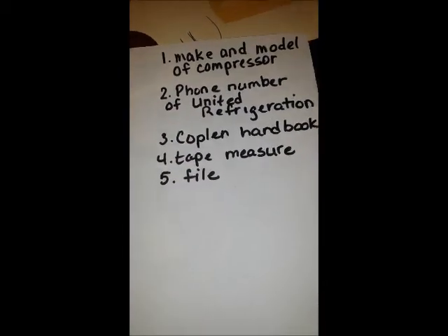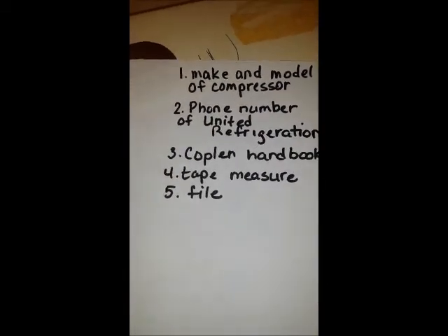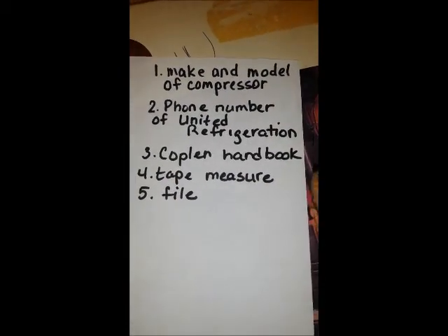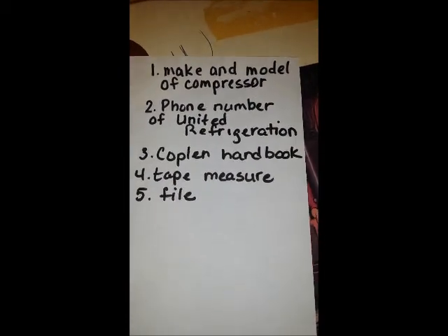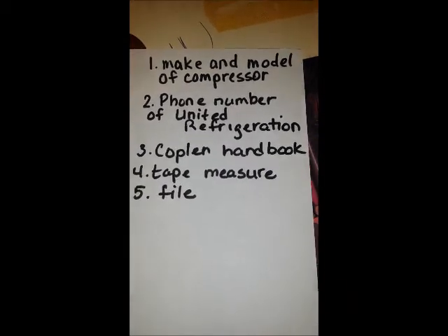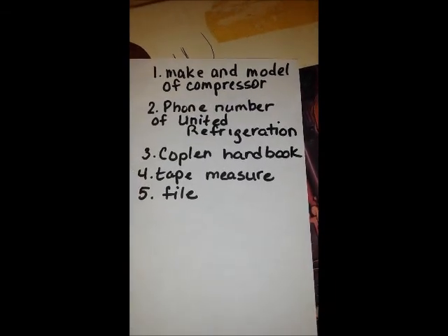You don't know how long it is or what the size of the capillary tube is or anything. So what you need to do is take the model and make of the compressor. If you have a Copeland handbook, you can look in there and it will tell you what the horsepower is and what the gas is for that particular unit. Or you can call United Refrigeration and give them the information on top of the Copeland or Tecumseh. They will tell you if it's 134A half horse or what it is.